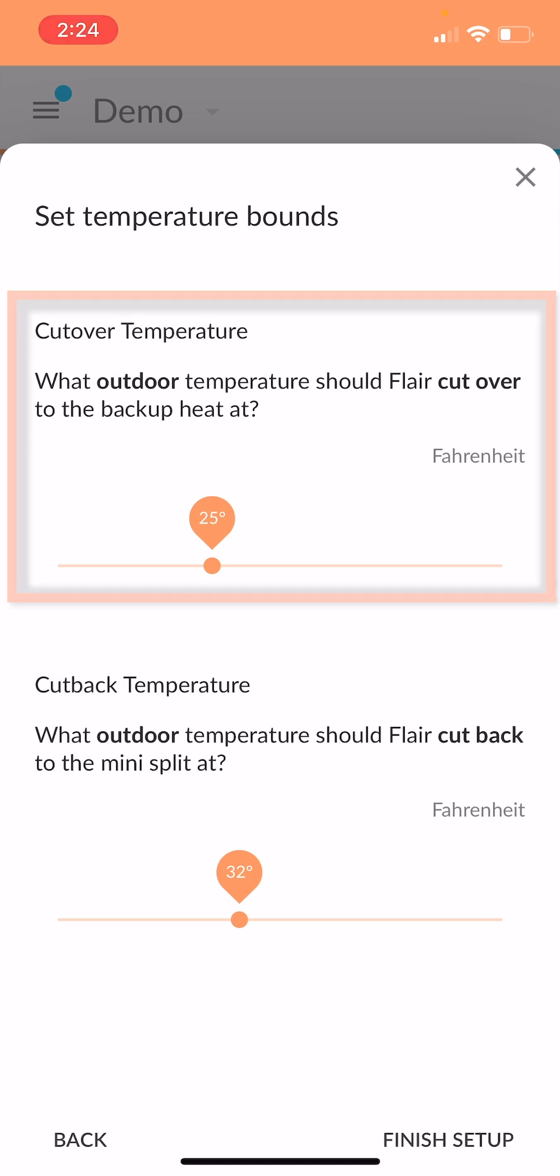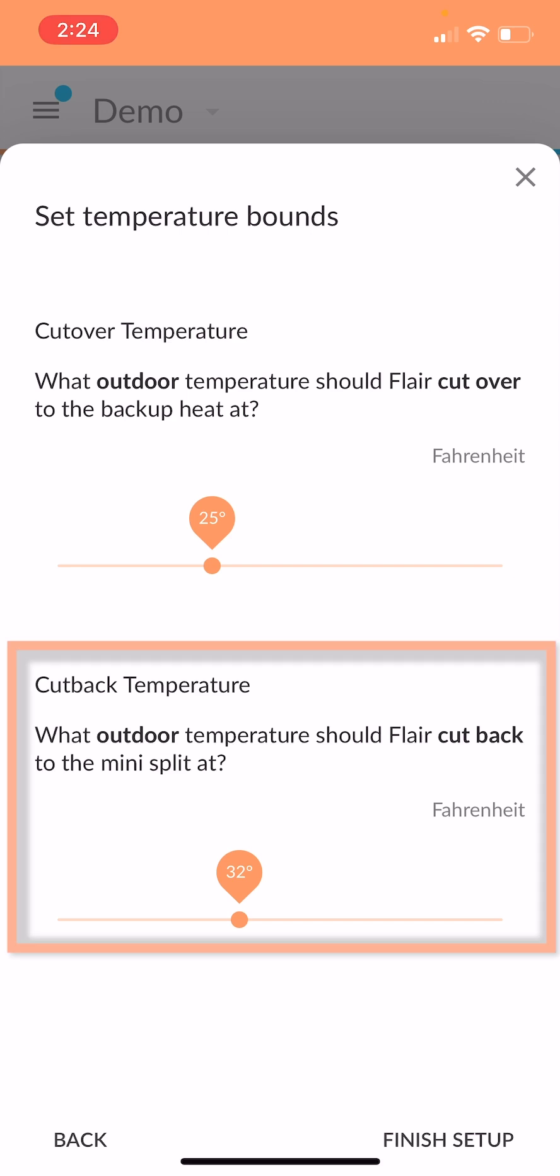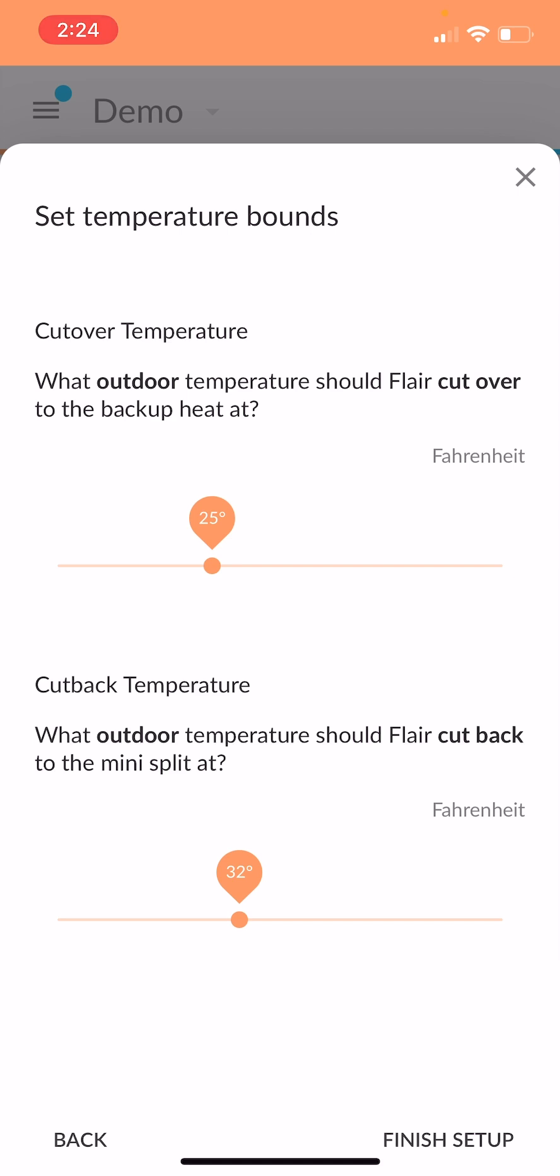And then we'll stay in that stage until the outdoor temperature gets back over the cutback temperature, at which point we'll go back to the first stage. I've got 25 and 32 here. I actually think those are pretty solid for my house. So I'm just going to leave that and hit finish setup. And we're ready to rock and roll.